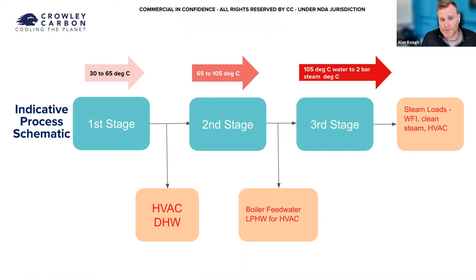The second stage goes from 65 to 105, producing water or atmospheric steam in a kind of reboiler arrangement. The third stage is pumping that atmospheric steam up to 2 or 3 bar steam to do something useful with it. Obviously, a lot of sites have existing steam infrastructure in place, and it's very expensive to rip all of that out and replace it with hot water.